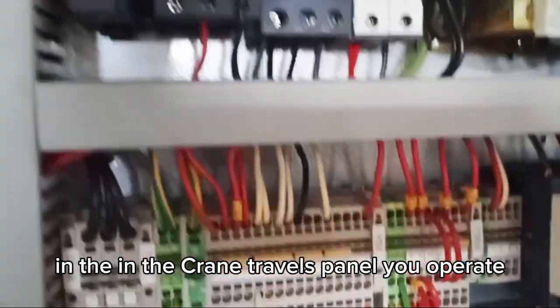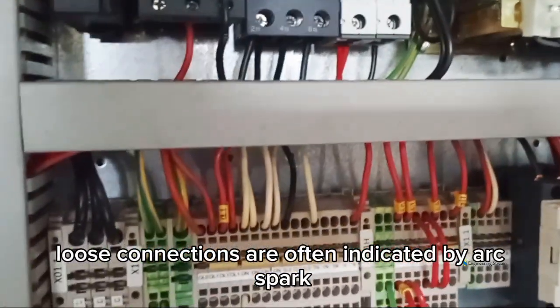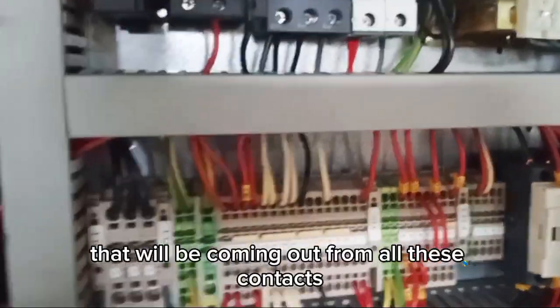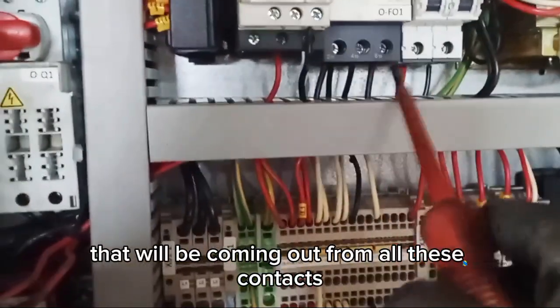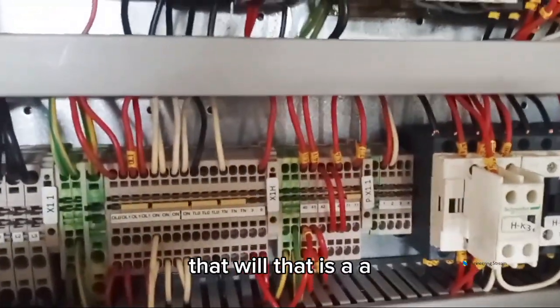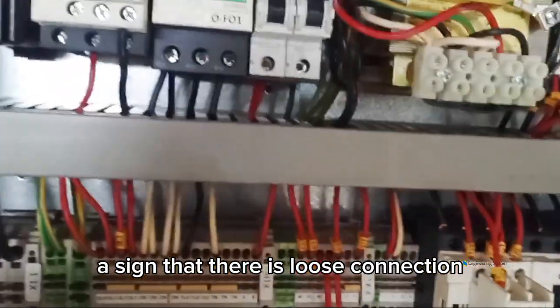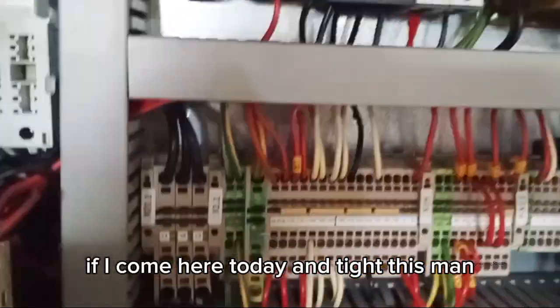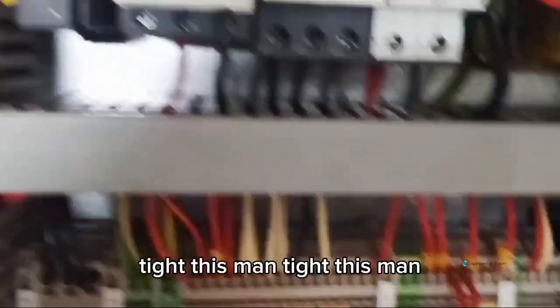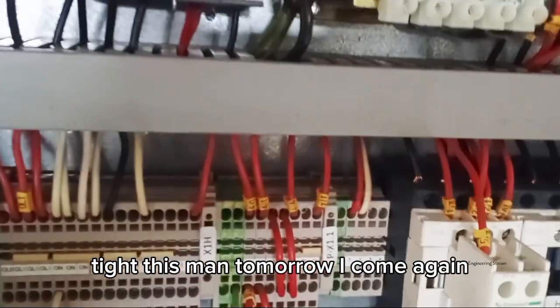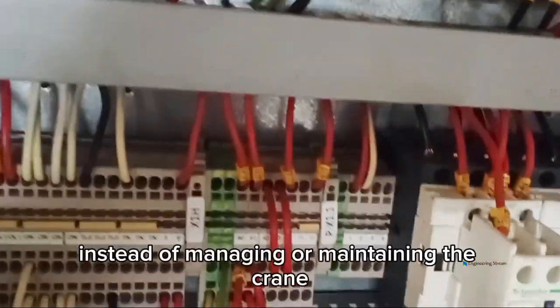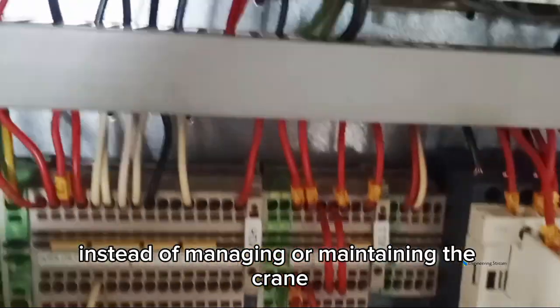Professionally, if you want to know if there is loose connection in the crane travels panel, you operate. Loose connections are often indicated by spark that will be coming out from all these contacts. That is a sign that there is loose connection, and then you tighten. If I come here today and tighten this, this, this, tomorrow I come again, I do same. You end up, instead of managing or maintaining the crane, you add problem to it.